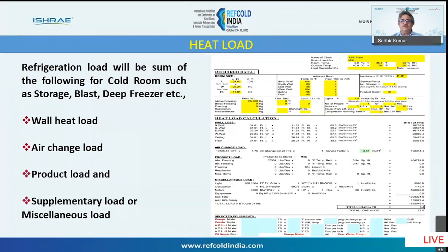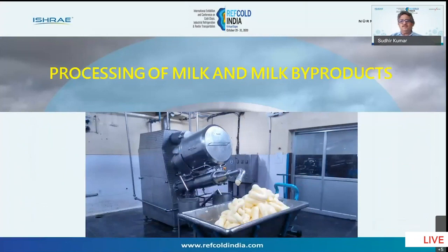The other heat load is the refrigeration load of the direct heat load. The direct heat load is basically a milk cold room, or it can be a butter deep freeze, or an ice cream deep freeze. So you need to have various parameters, like the ambient temperature, the door opening, the incoming temperature, and the product load. Supplementary or miscellaneous load is the number of fans and the number of people working. So this is how we calculate the heat load for the direct load. Once you calculate both the loads, the indirect load and the direct load, then we can design a refrigeration plant.